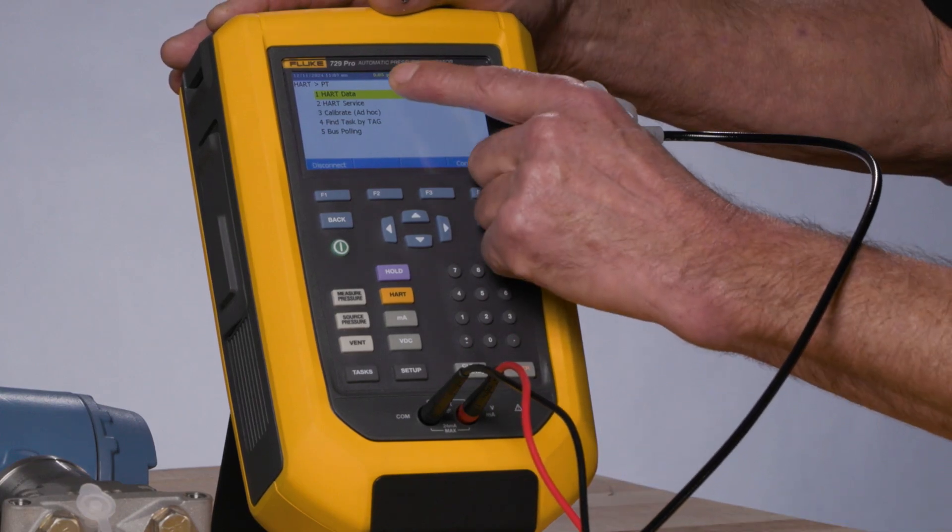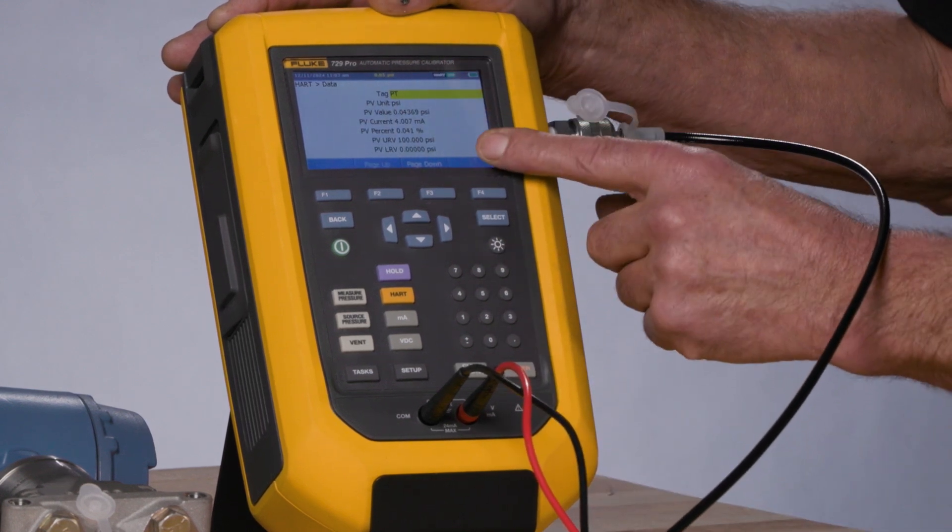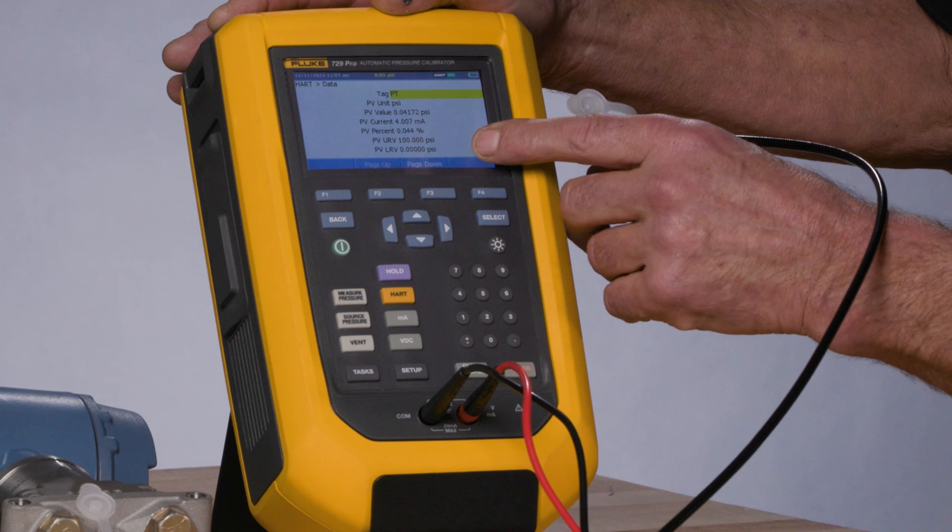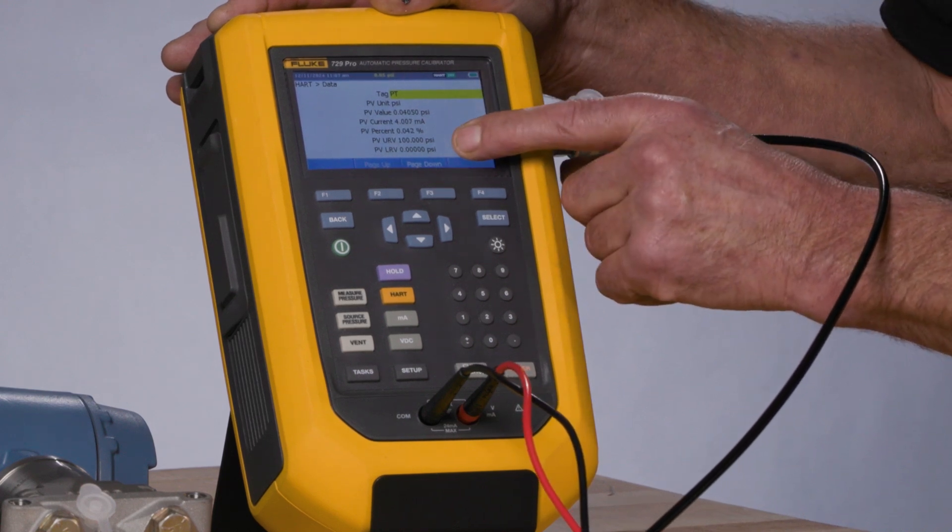So if I select, notice initially we're on HART data. If I select HART data, we can see here how the device is configured via the HART communication, and we can see that this transmitter has a range of 0 to 100 psi.